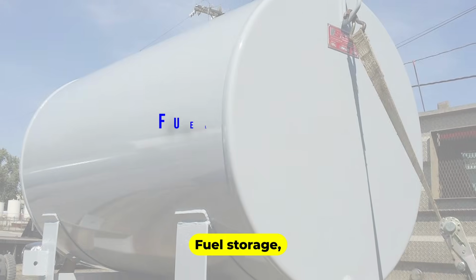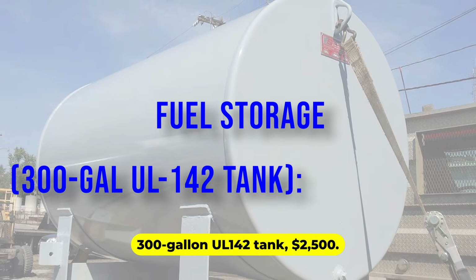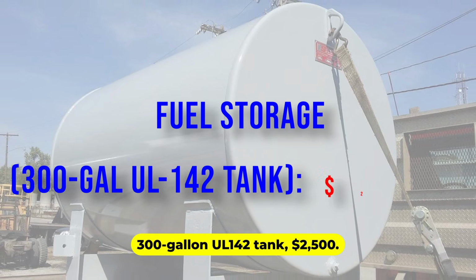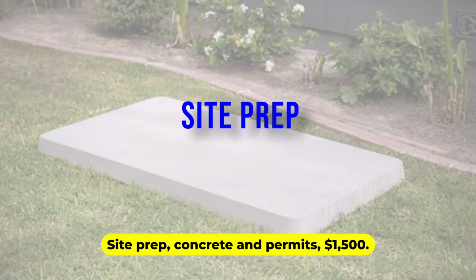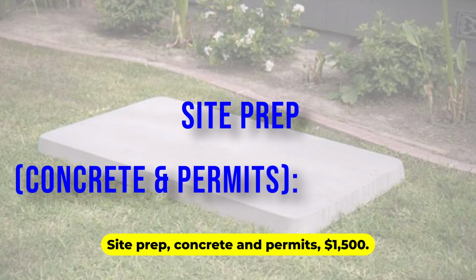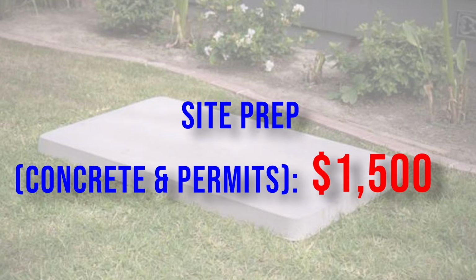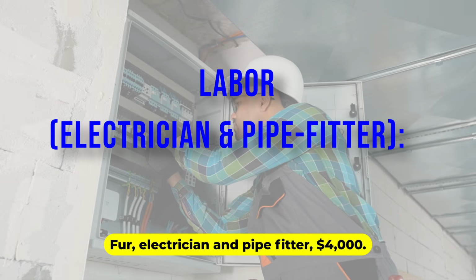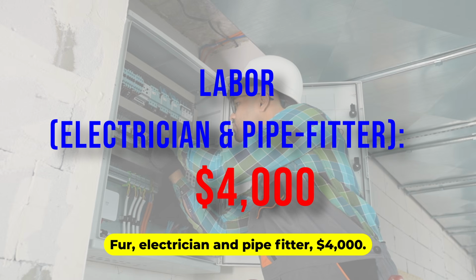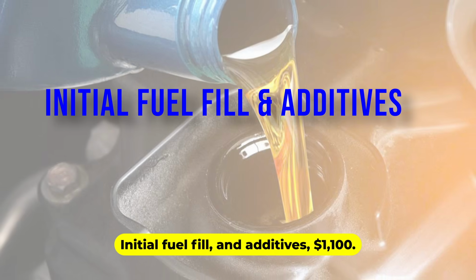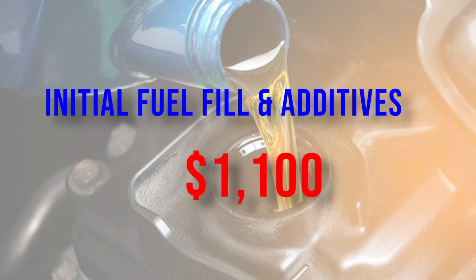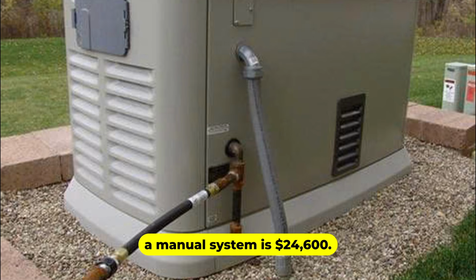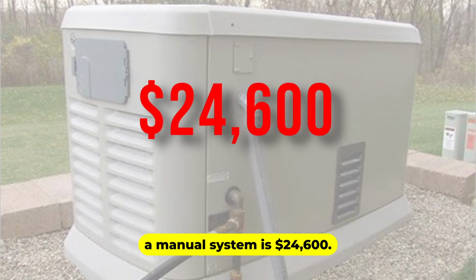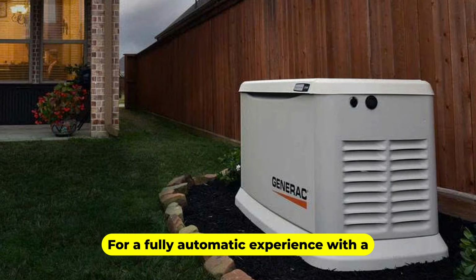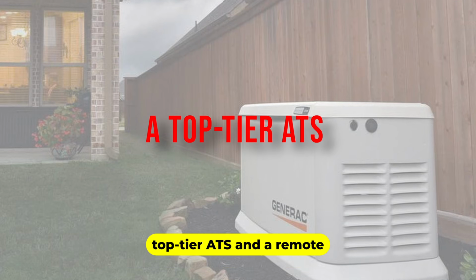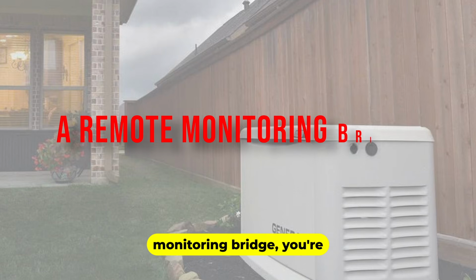Fuel storage, 300-gallon UL 142 tank, $2,500. Site prep, concrete and permits, $1,500. Labor, electrician, and pipe fitter, $4,000. Initial fuel fill and additives, $1,100. Your total project cost for a manual system is $24,600. For a fully automatic experience with a top-tier ATS and a remote monitoring bridge, you're looking at $27,700.